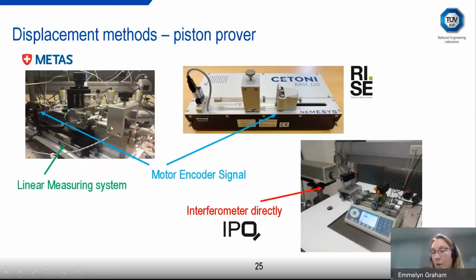METAS have built their own custom-built syringe pump, where they can record and get information on the displacement and relate that back to velocity movement of the syringe. And IPQ are using a more advanced technique using an interferometer, which is directly used with the actual syringe pump. It is a more expensive method, but it does give you much lower uncertainties.